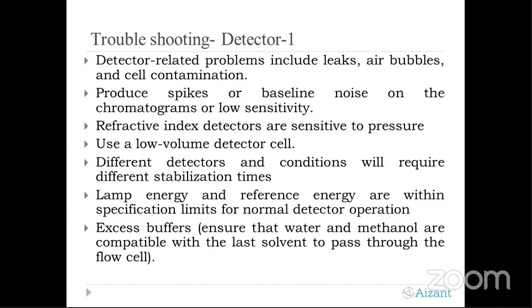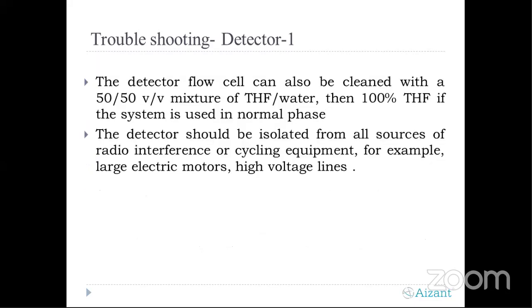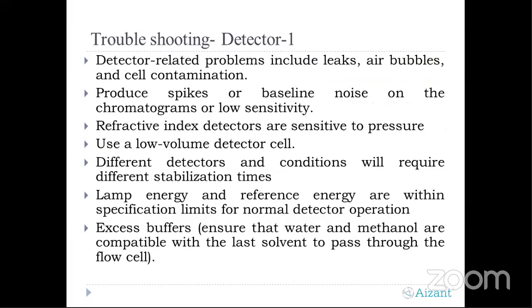That can resolve it. Cell contamination: what do we mean by cell contamination? If you are analyzing a method in which the component is soluble in a particular solvent, and it is passing through your system, there is no challenge. But in laboratories, when we start washing the system, we never think about whether the sample we are analyzing dissolves in this washing solvent or not, and we directly start washing the system. Because of the incompatibility or insolubility of this component in this particular wash solvent, it will contaminate the whole system, not only the detector, but your tubings, your pump, your injector seal, everything.